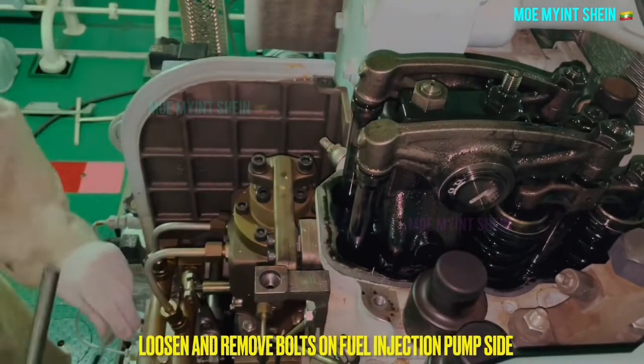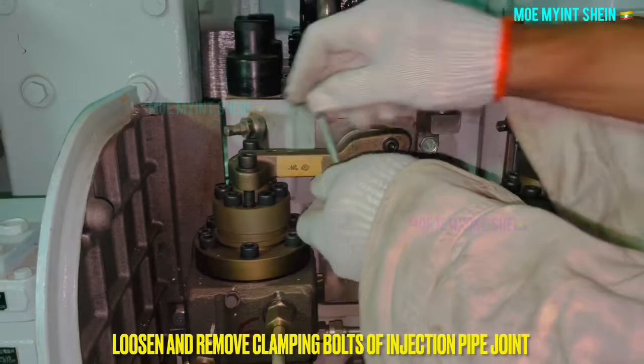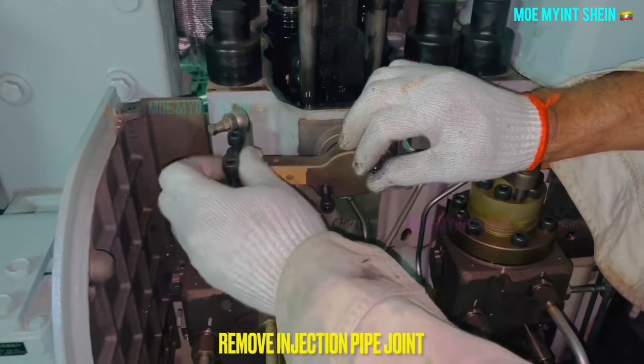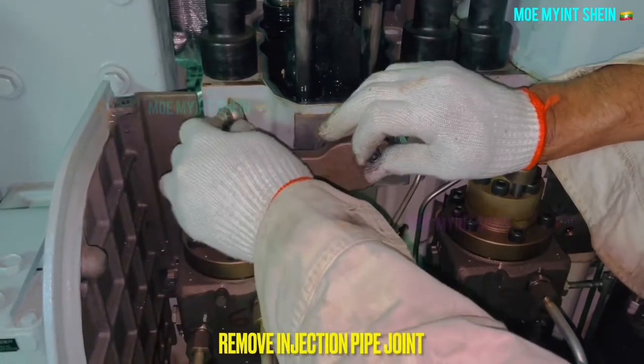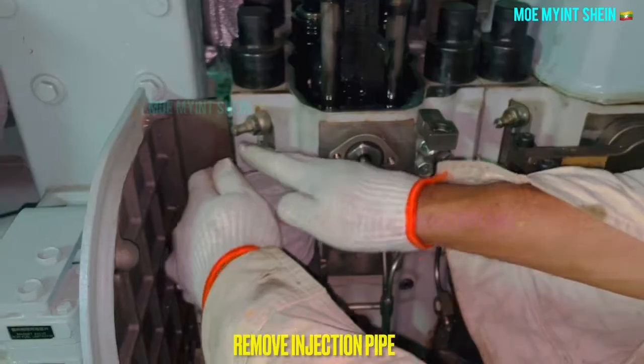Loosen and remove the bolts on the fuel injection pump side. After that, loosen the clamping bolts of the pipe joint on the cylinder cover. Remove the injection pipe joint after the clamping bolts on both sides have been removed. Now you can pull off the injection pipe.